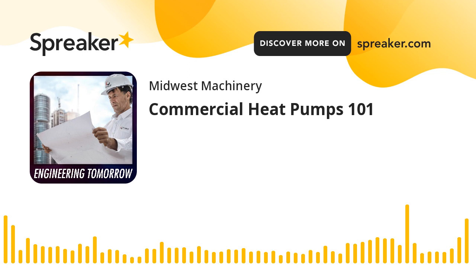Usually we see about 15 years is the life expectancy of a water source heat pump. They're pretty good about the big parts of a heat pump: the compressor, the fan motor, and then the brains, the controls, and the refrigeration pieces. Usually if a compressor goes, you just switch out a compressor and go on your way. But when you start losing compressors and your refrigerant piping starts kind of corroding away and getting leaks all the time, then it becomes more cost effective to just replace the whole unit.